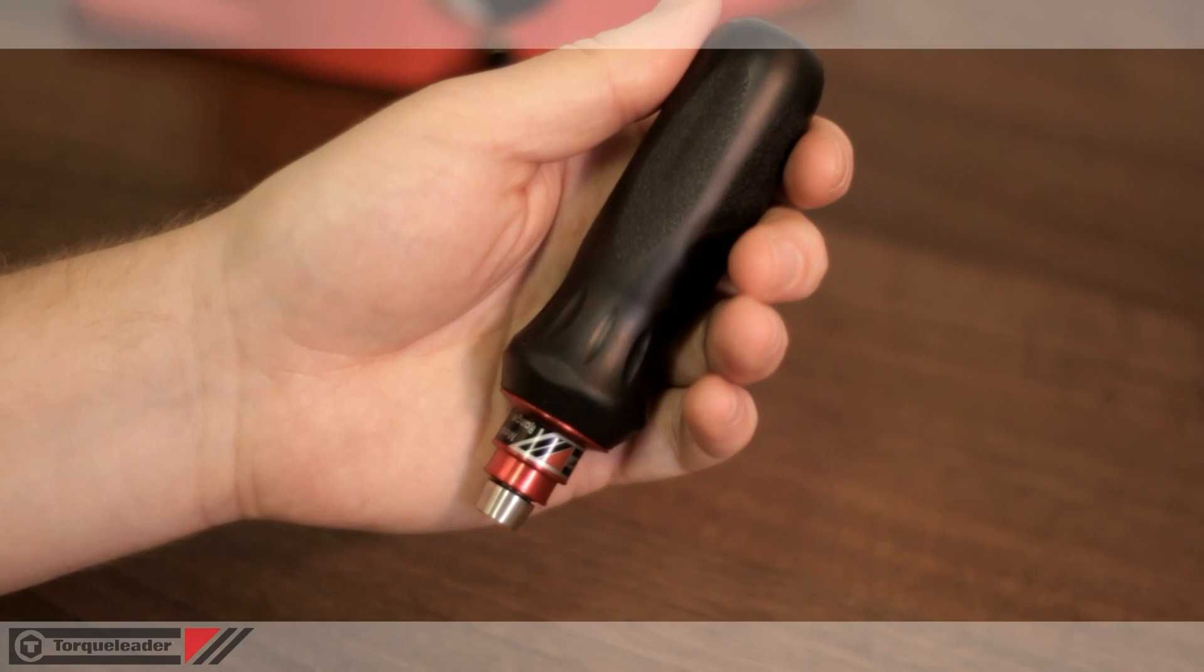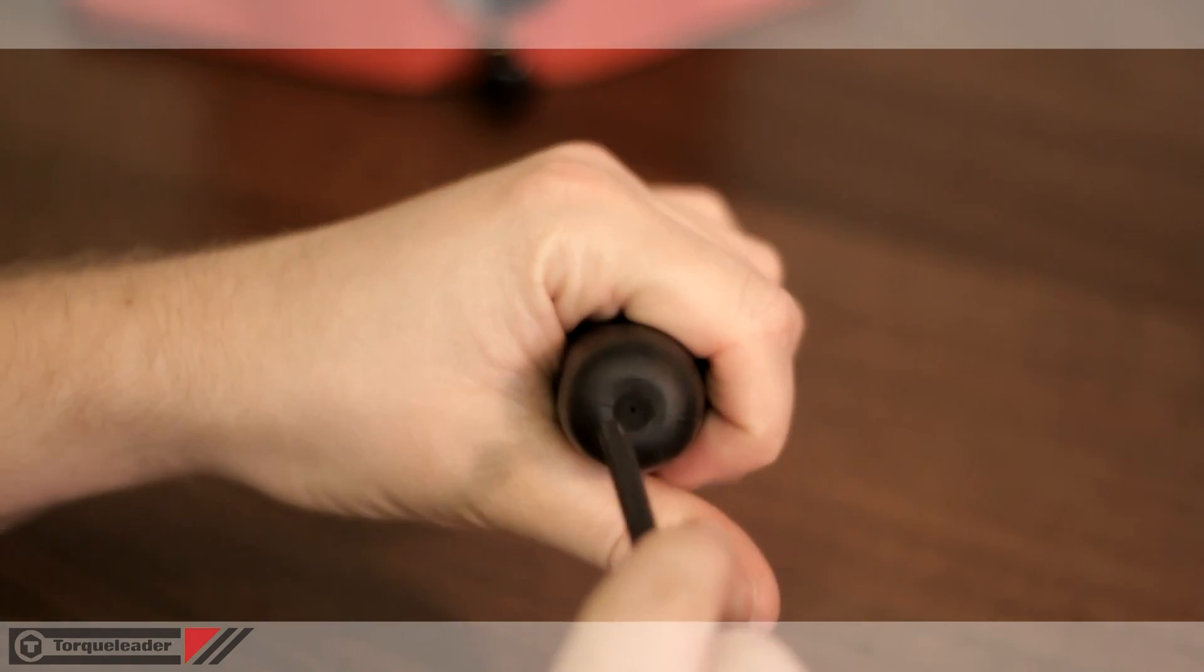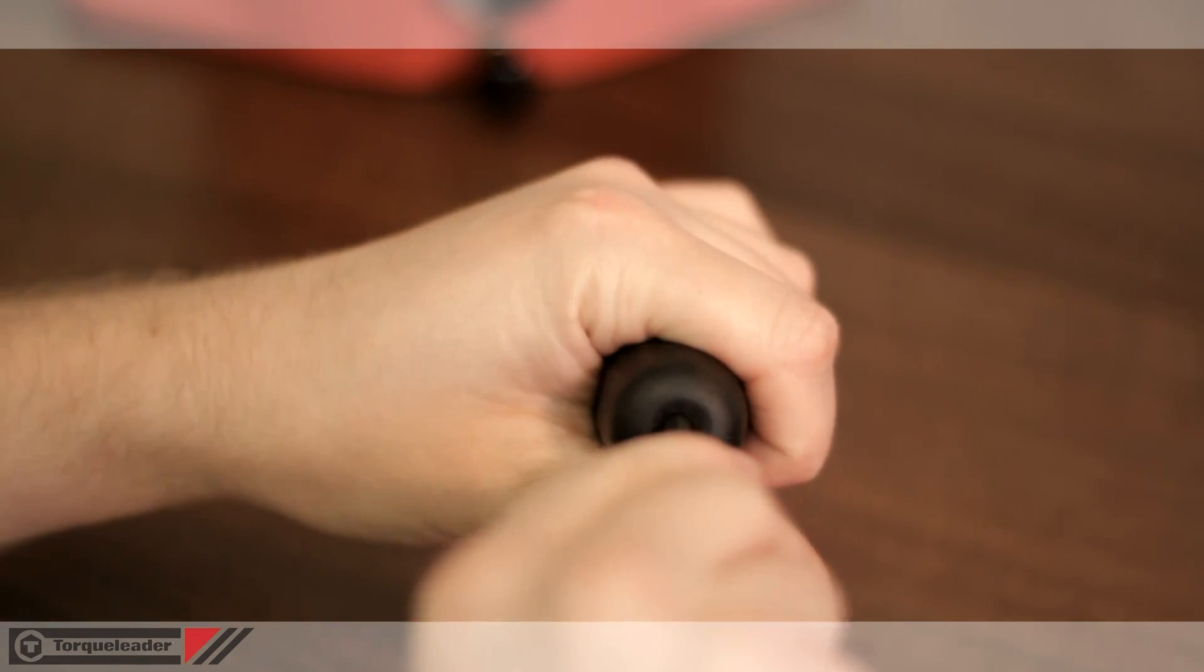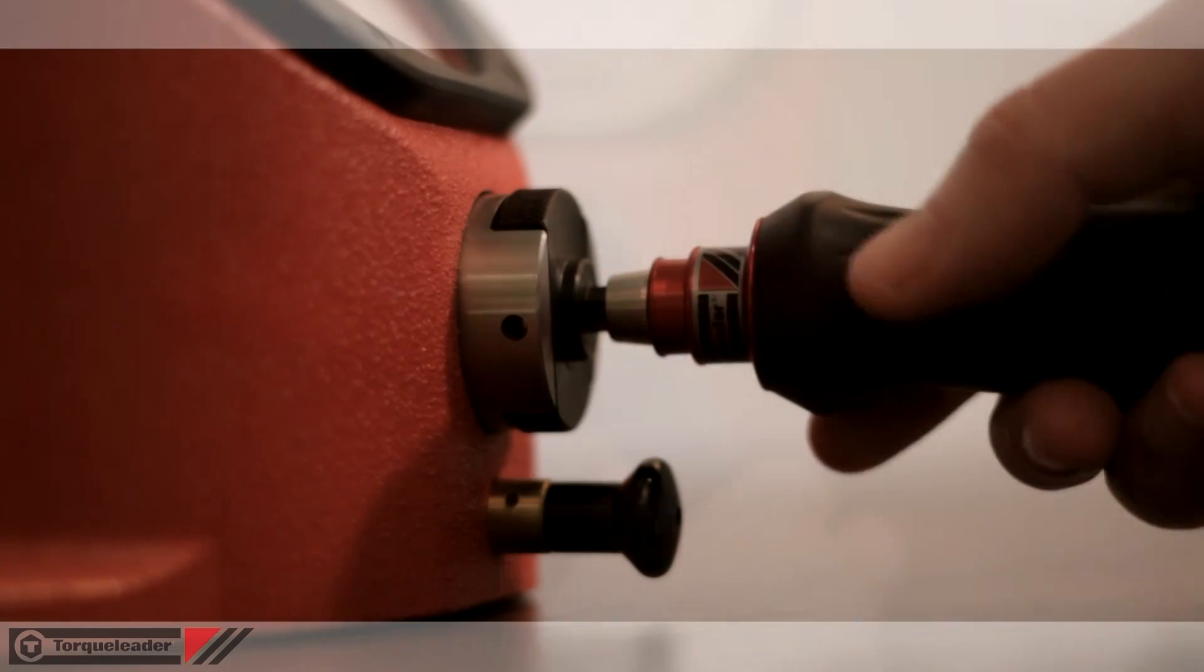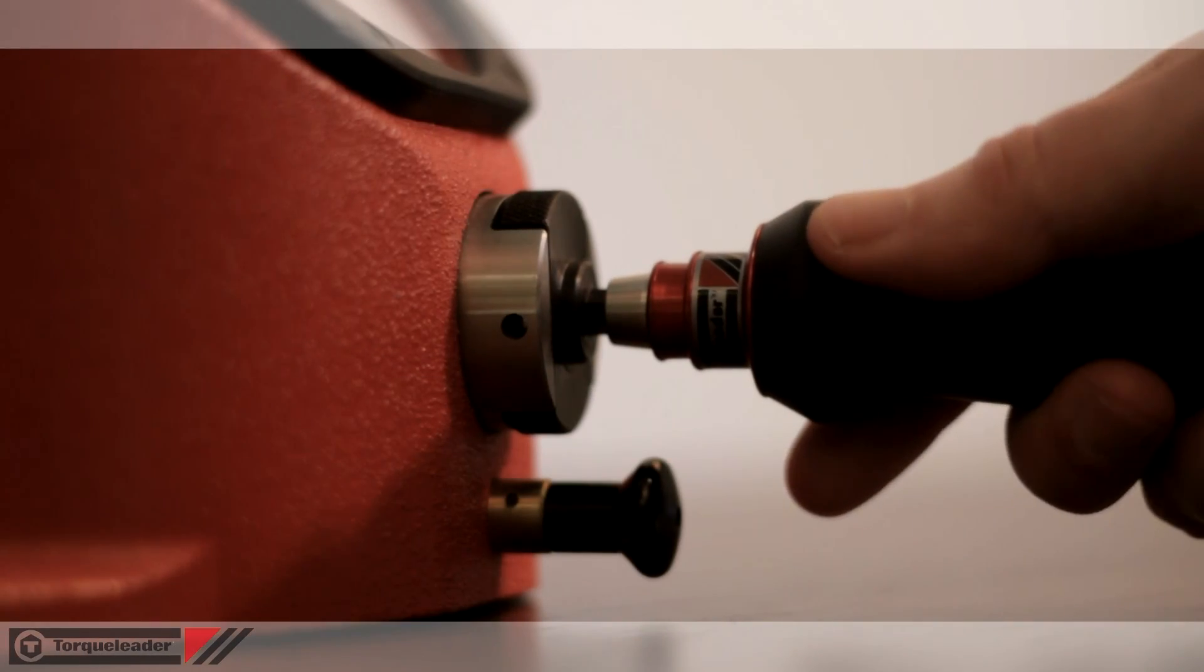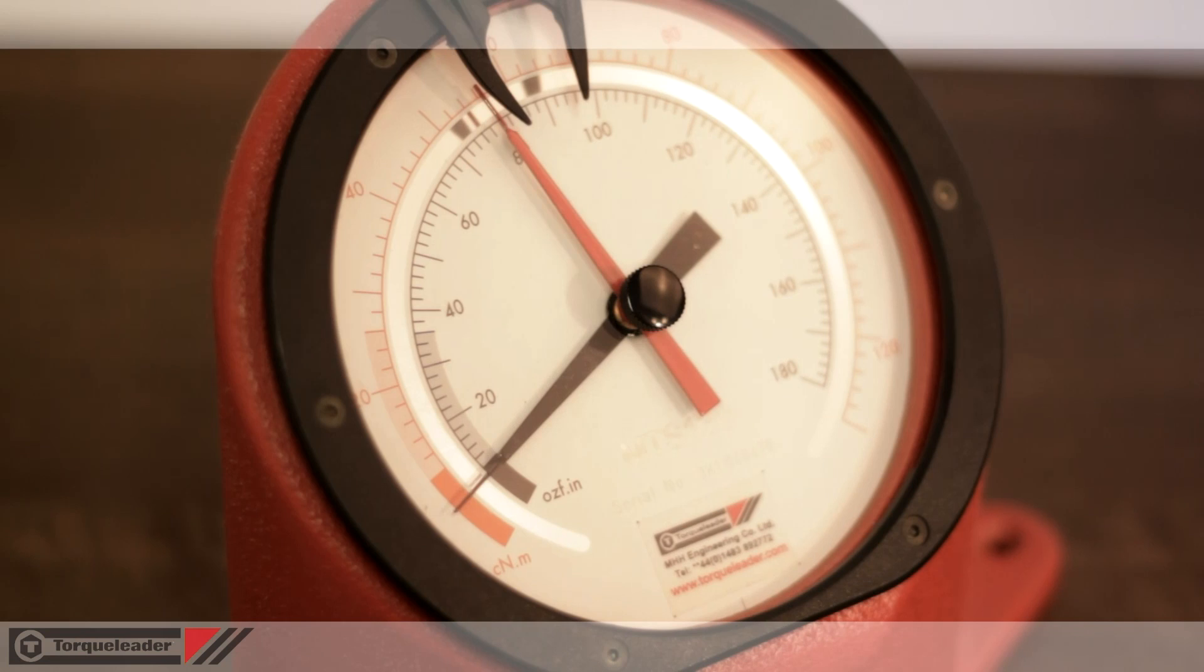A five millimeter hexagon key is pushed through the pinhole at the end of the hand grip. This engages with the adjusting mechanism underneath. Rotate the key until the correct value is shown on the analyzer.